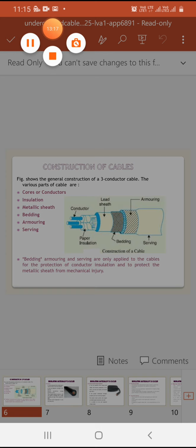Now I want to discuss briefly the insulating materials for cables. As we know, insulating material for cable is considerably important, so we should understand the properties of insulating material. As per the slide shown, the first property is that high insulation resistance should be offered by the insulating material to avoid leakage current. Then the insulating material should have high dielectric strength to avoid electrical breakdown of the cable.